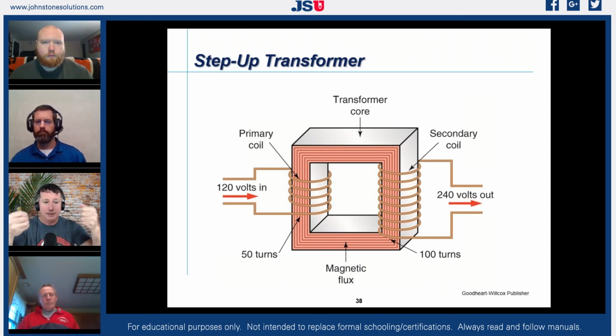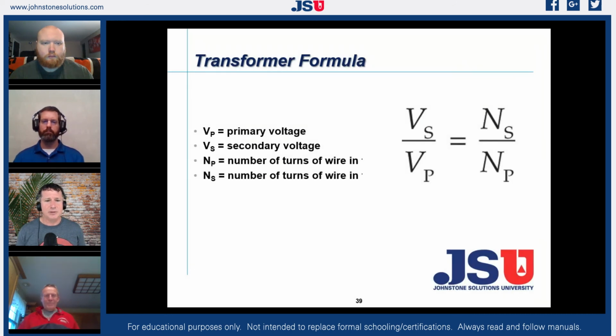You have two completely separate magnetic fields on a transformer. They're very isolated. If you take the wrap off the side of a transformer, you can see both of those windings—they're insulated by a plastic plate. I don't think I have that in this one, but I know I've got some slides that show that. So we can actually look at those windings independently on a transformer, and I encourage you guys to do that.